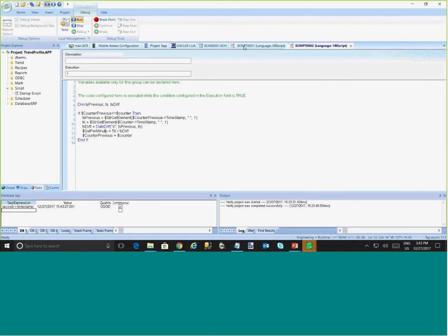So those are the two main methods: either instantaneous, or granulated on a period of time, per period of time. And it doesn't need to be 1 minute. It can be every 10 seconds, but the difference is you multiply by the constant, and if it's every 10 seconds, divided by 6, because that's the number of pulses you expect in 60 seconds, for example. So either way, you can calculate the instantaneous value, or you can aggregate after a period of time.